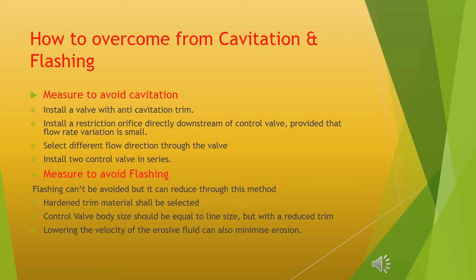How to overcome cavitation and flashing: install a valve with anti-cavitation trim; install a restriction orifice directly downstream of the control valve, provided that flow rate variation is small; select a different flow direction through the valve; install two control valves in series. To avoid flashing: flashing cannot be avoided but it can be reduced through these methods — hardened trim materials shall be selected; control valve body size should be equal to line size but with a reduced trim; lowering the velocity of the erosive fluid can also minimize erosion.